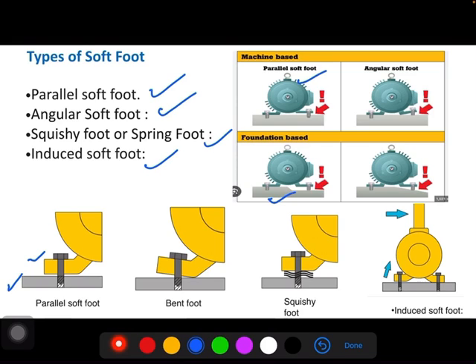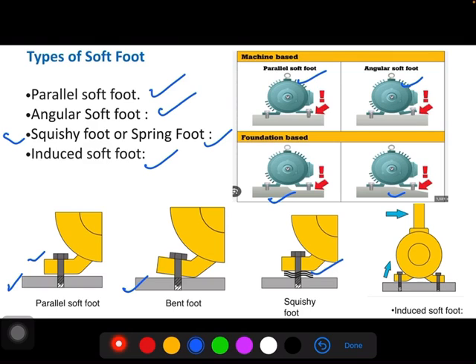Second is angular soft foot. When the feet of the machine and base are inclined to each other, it is called angular soft foot. In this case also, if the feet of the motor is inclined or the concrete or base is inclined, you face angular soft foot. Third one is squishy soft foot, which you can also call spring foot. When you use more number of shims in between the machine frame and the base, and the shims are bent or there is dirt or dust in between the shims, then it causes spring foot or squishy foot.